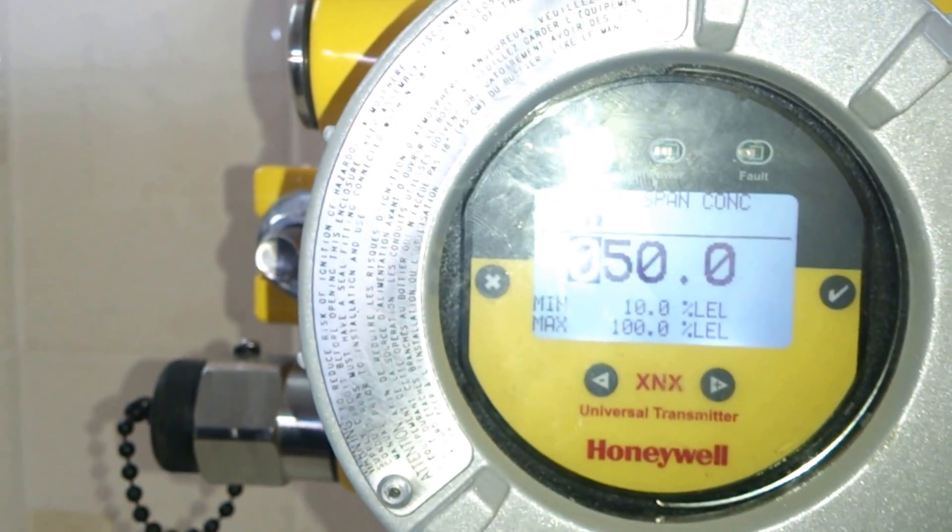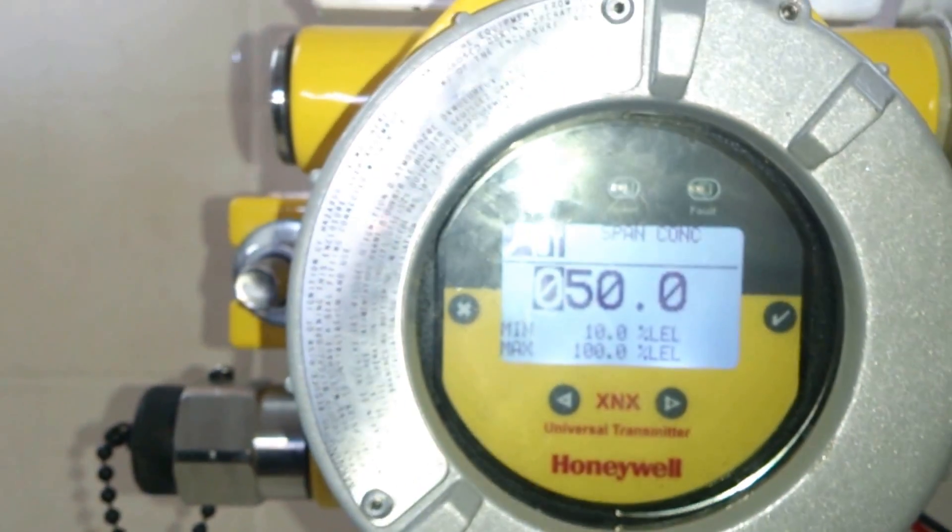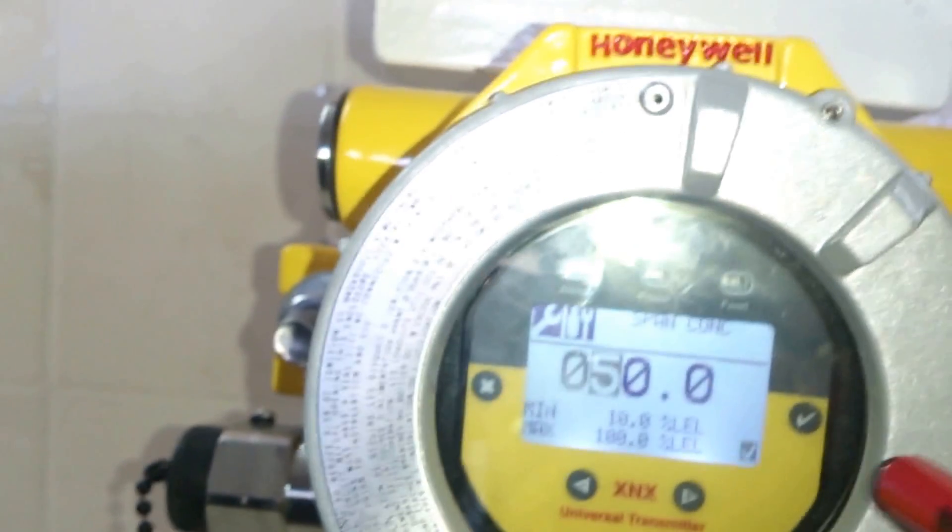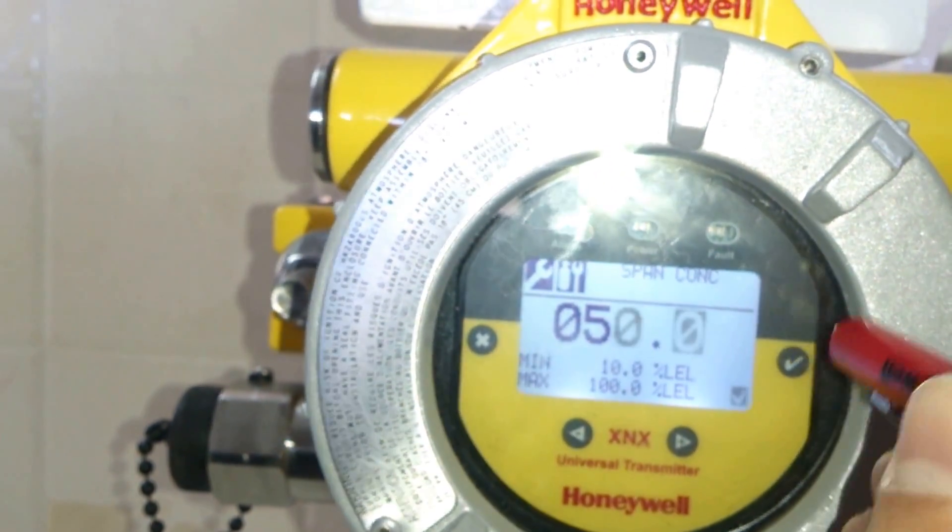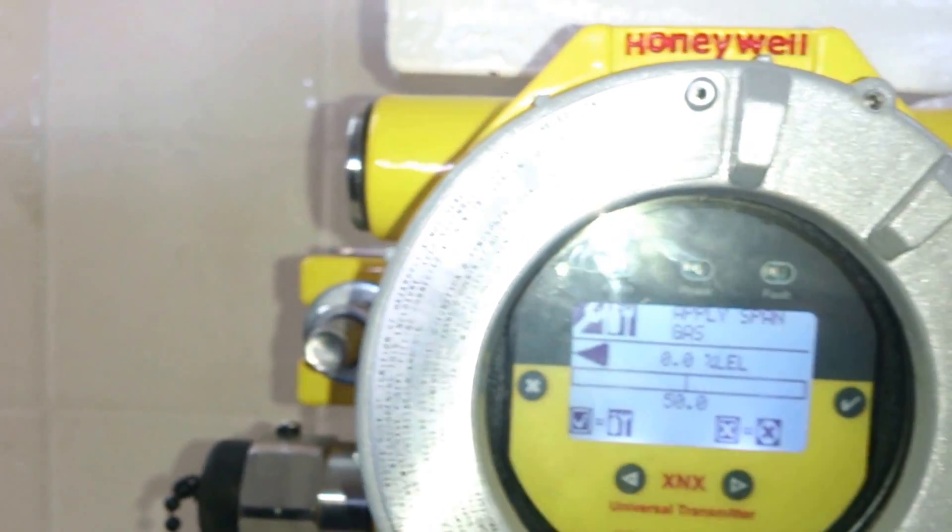Next is span calibration. Span calibration has to be set to 50%, as the cylinder rating is 50%. Once the value is set, that is 50%, now we apply gas using the calibration cup and gradually increasing the regulator knob. Once the gas is applied, we see increase here in the LEL level.